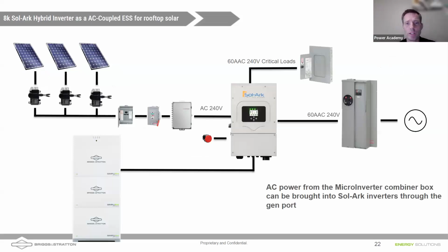So I'm showing an example. Okay, here's where I've actually got the amperages correct. Here I'm showing an 8K Sol-Ark, and we are AC coupling that microinverter existing solar into this 8K Sol-Ark. In a grid down event, what would happen normally for this array, before we made the change to a Sol-Ark with AC coupling, is that the whole array would go down. So in a grid outage without the Sol-Ark there, the Enphase solar array provides zero backup.